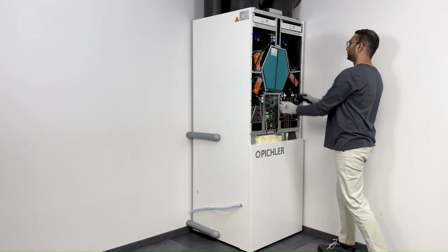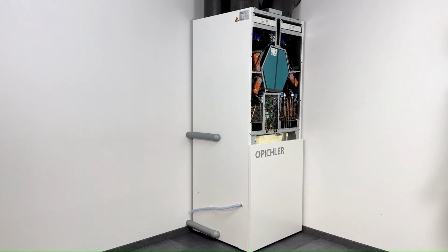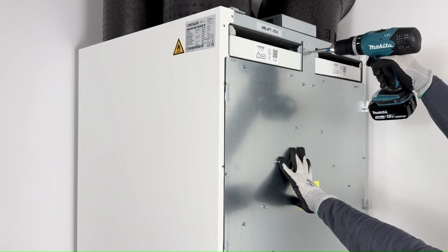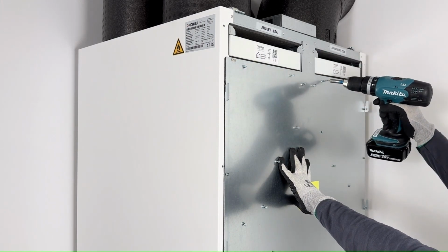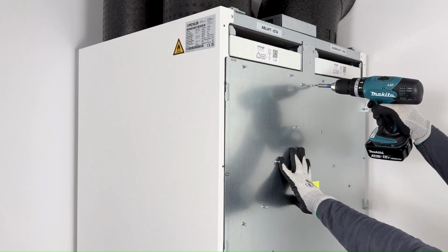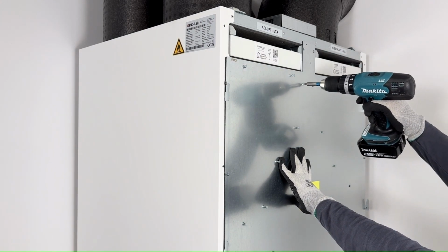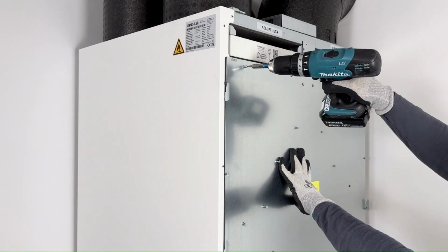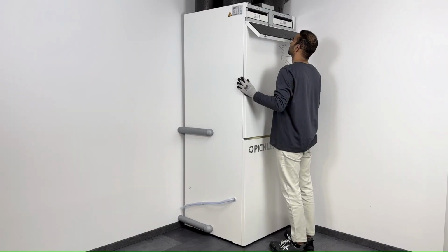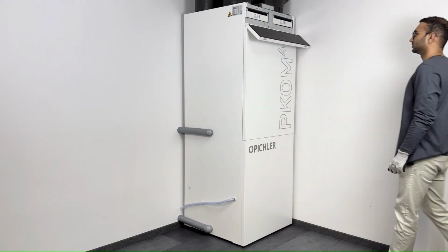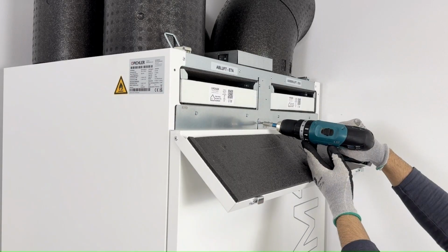It's crucial to ensure that the sealing profiles are properly seated. Then delicately fasten the sealing plate back in place by tightening all securing screws. Please keep in mind that only a cordless screwdriver with a slip clutch and a torque setting of 5 is allowed to be used. After that, put back the front hood of the heat pump. Then, fasten the safety screws tightly.